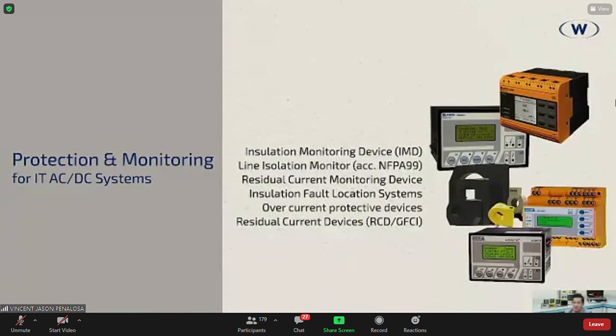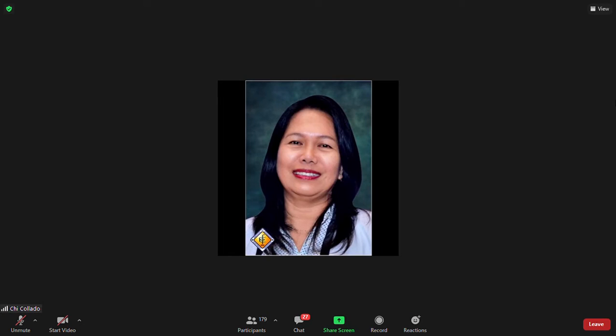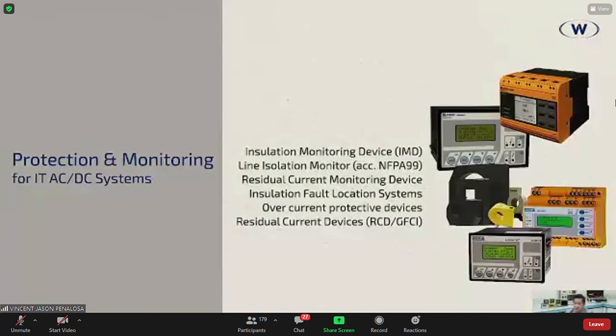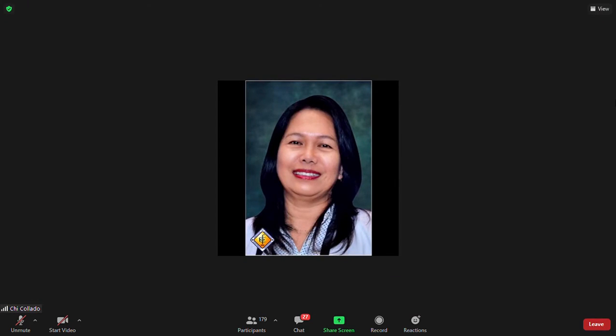You have insulation fault location systems, overcurrent protective devices, and residual current devices. RCDs is what they term GFCIs, ground fault circuit interrupters, in Europe. In Europe, they call it RCDs. In the US, they call it GFCIs.